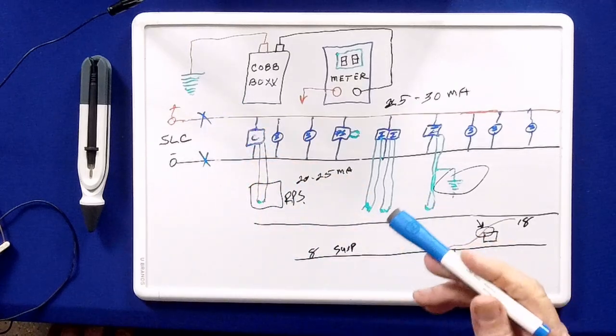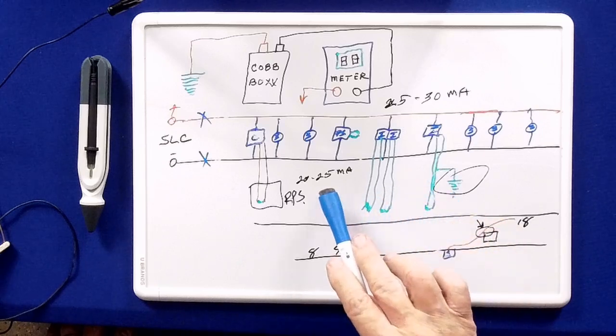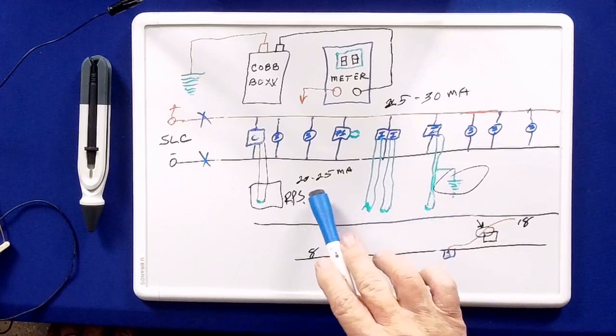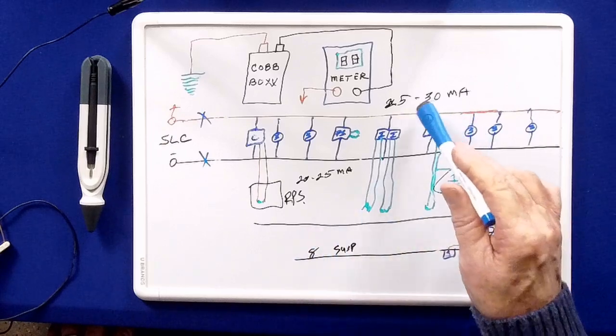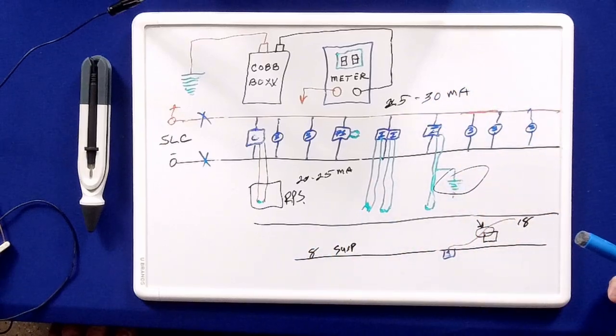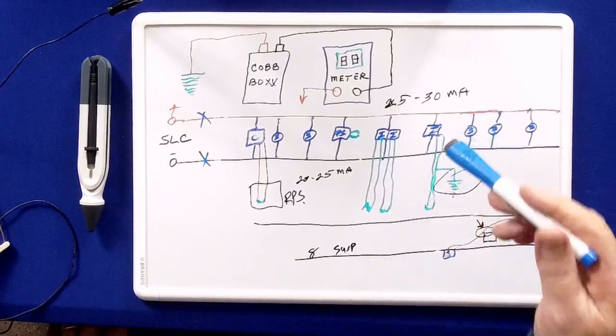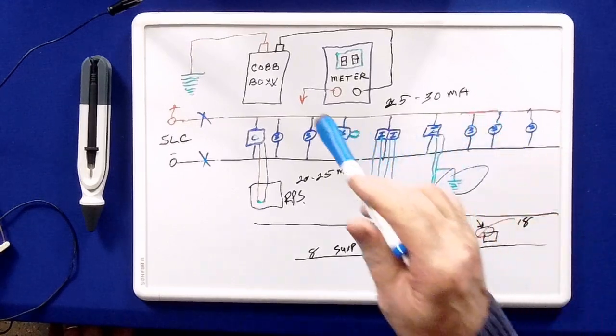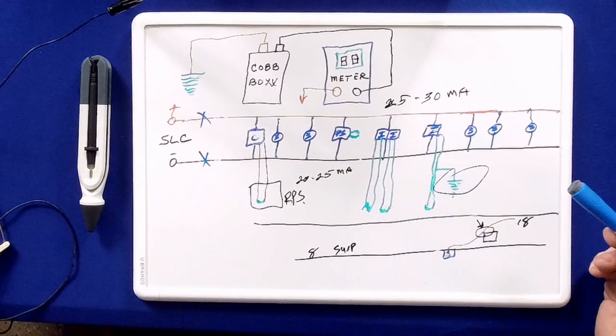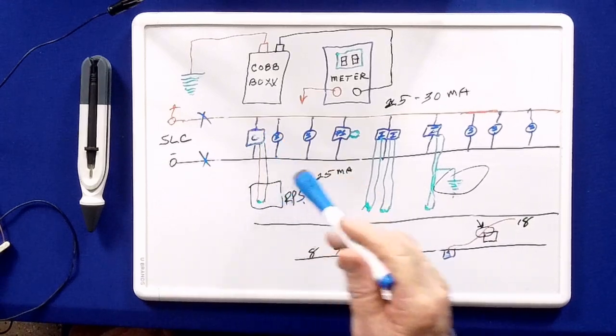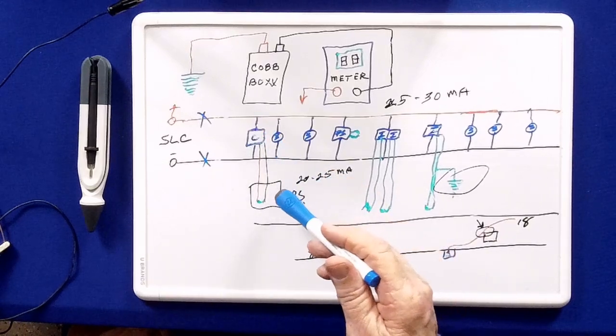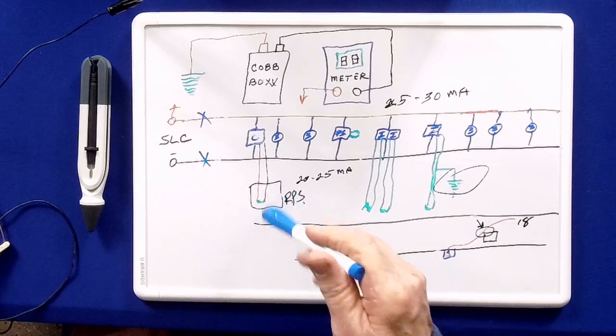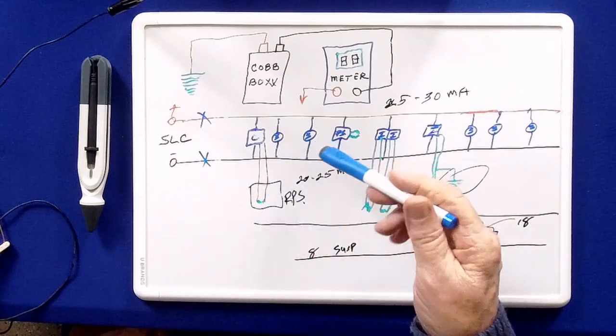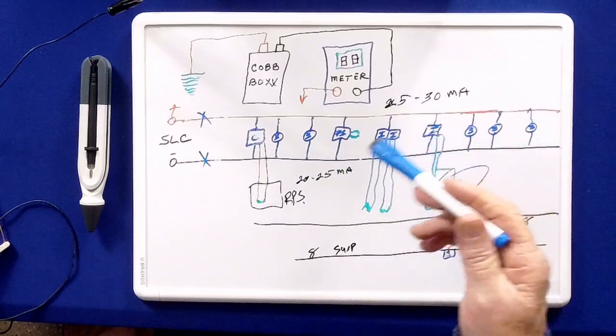Now, when I read either side of a SLC and I see, and this is approximate, it'll vary, say 20 to 25 milliamps on one side and 25 to 30 milliamps on the other side, and not the full 95 to 100 milliamps that you'll see on a short from this box, then I know it's a module. And this is why I know it's a module. Number one, control module. Usually a short, very short circuit going into an RPS, and the module may even be in the RPS. Smoke detectors, they have no external circuit. So that's a no right there.